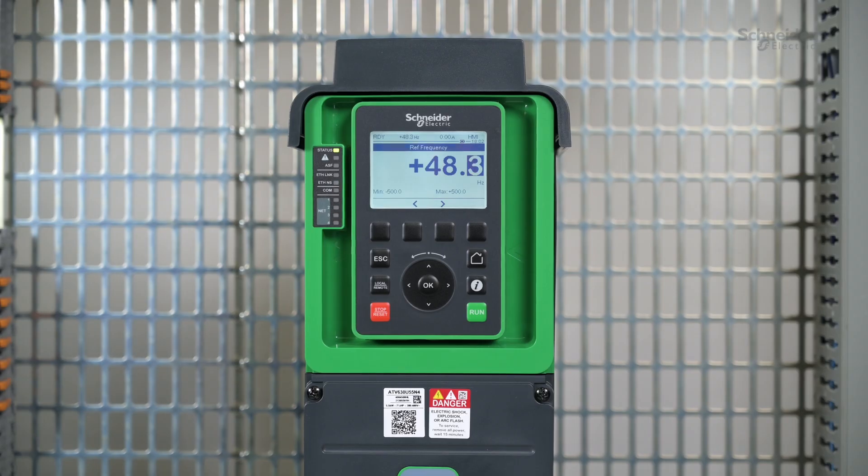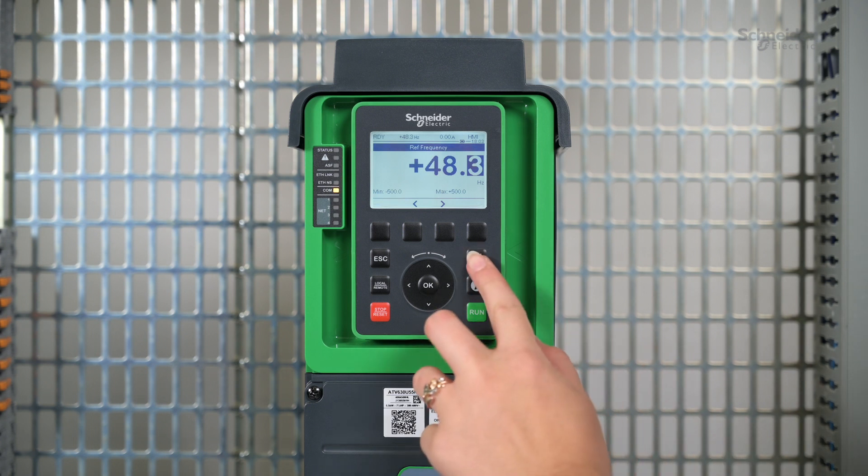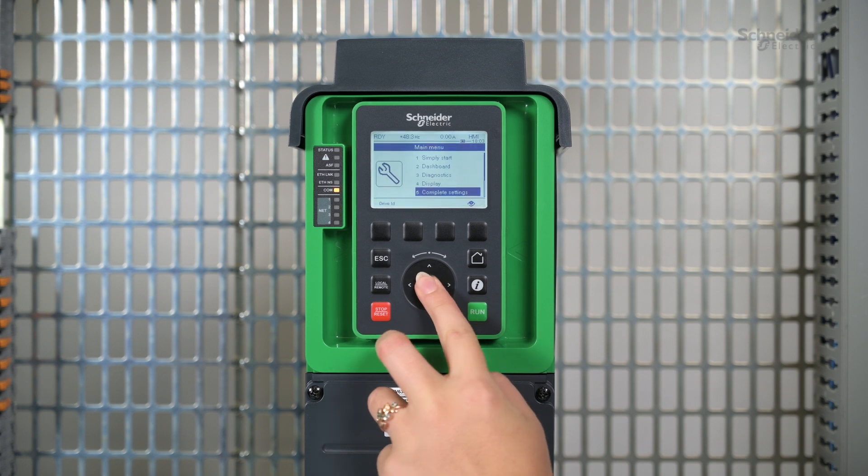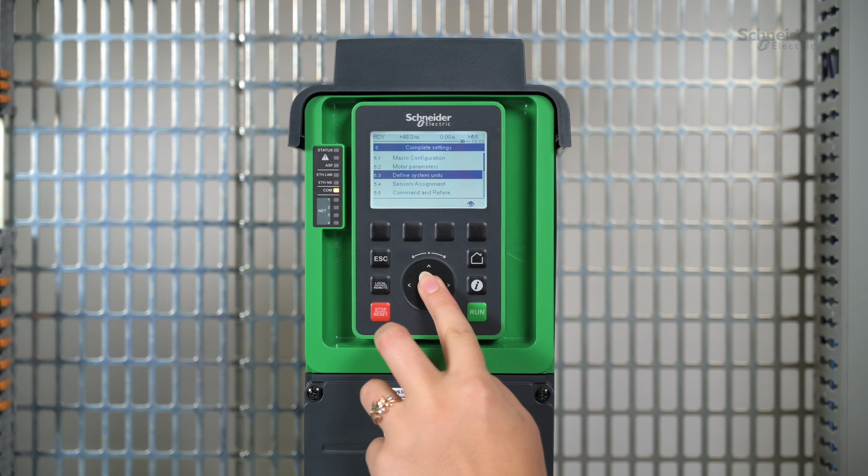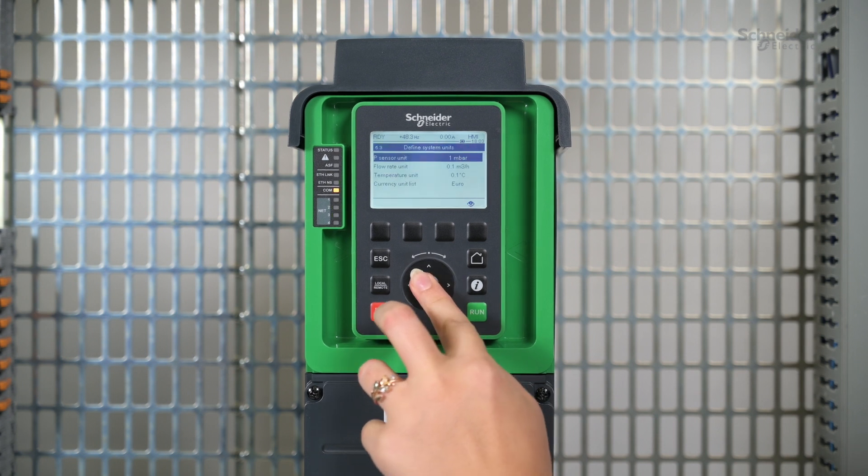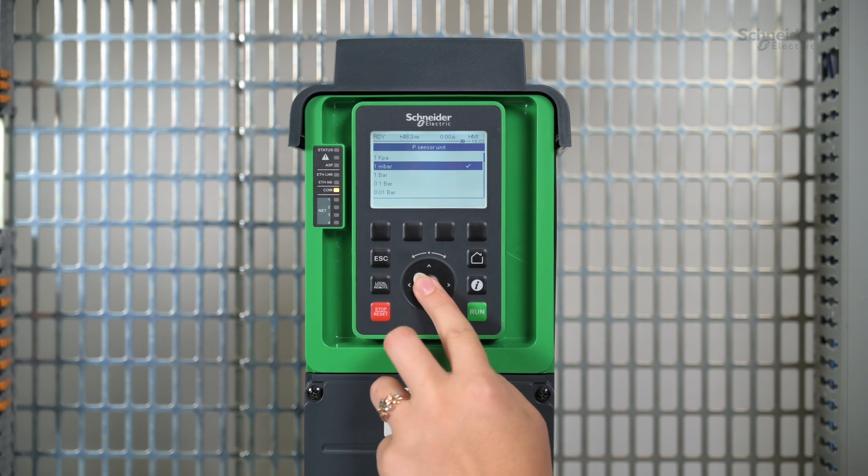In our example, the sensor is connected to AI3 and assigned to the pump flow value. With the graphic display terminal, perform a scaling to be more accurate. Go to complete settings menu, then define system units. In our example, with the pump selected, we change the unit to millibar.